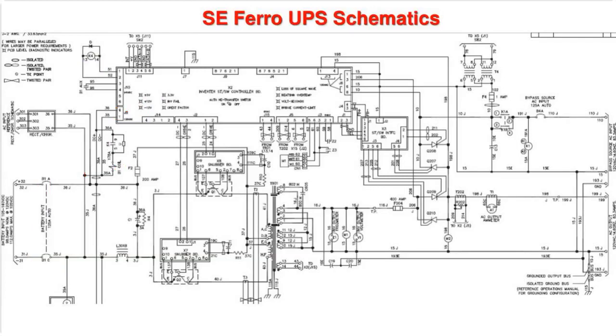We do have a circuit inside the inverter that says, let me just say, this is the inverter static switch, and this is the bypass static switch. When we trip this breaker at the 105 volts level, we send a signal and turn on the bypass static switch a few milliseconds before we trip that breaker, to make sure we transfer to bypass before that battery input breaker is tripped.